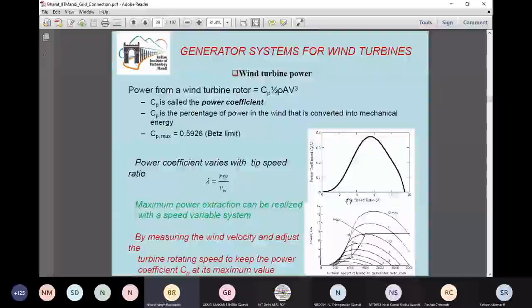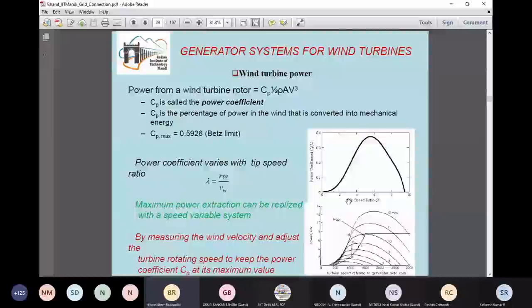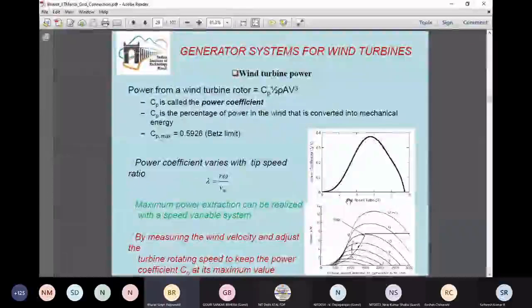So V is continuously changing. Based on this change in V, if we are able to make our system a variable speed system, then omega can also be changed. So the tip speed ratio, where the tip of a rotor blade is moving with R omega, is the ratio with V, where V is the velocity of the wind. And once we are able to control this lambda, we can continuously operate at the maximum point of this curve, which is shown in the right-hand side top figure, power coefficient versus tip speed ratio. Hence, a variable speed system allows us to always work at Cp maximum.